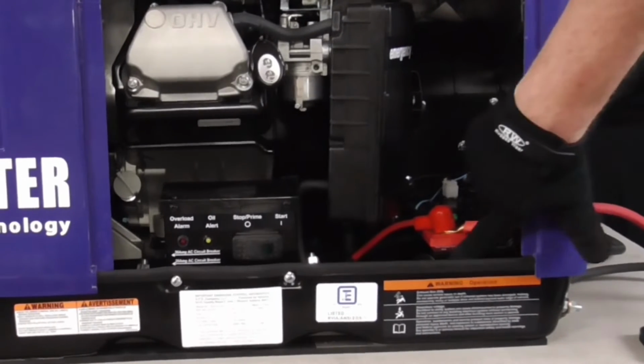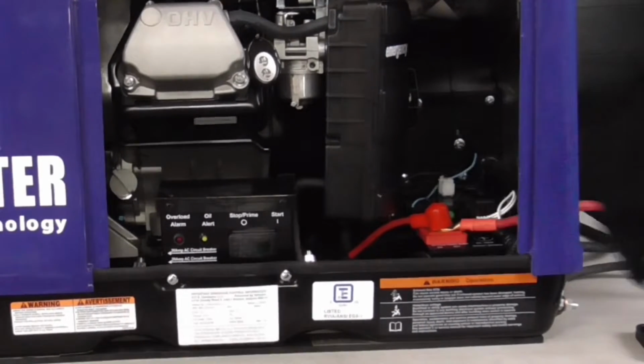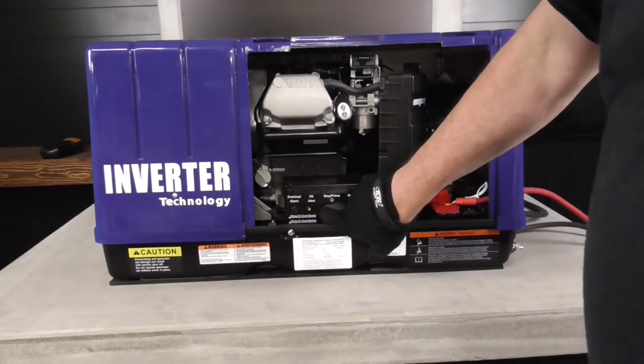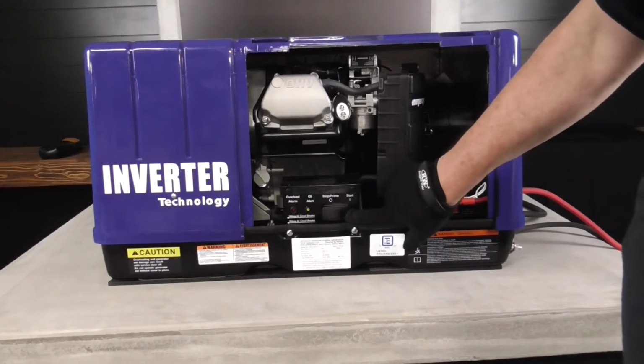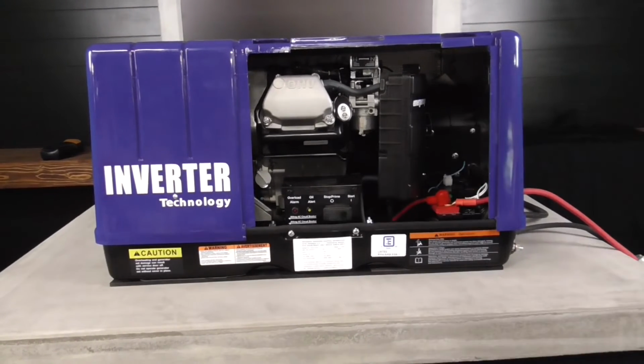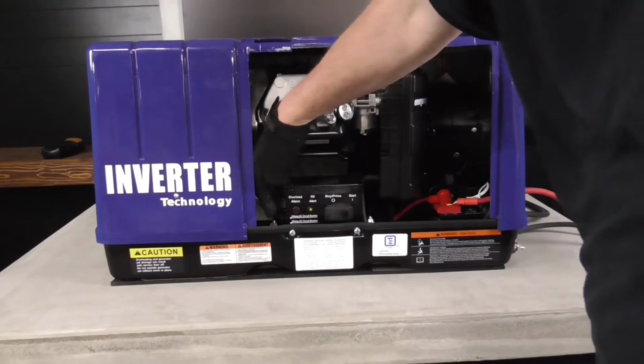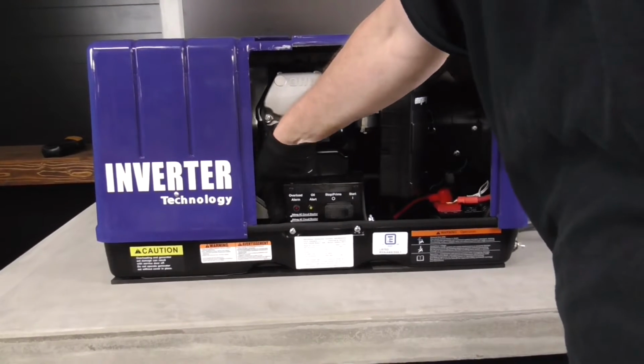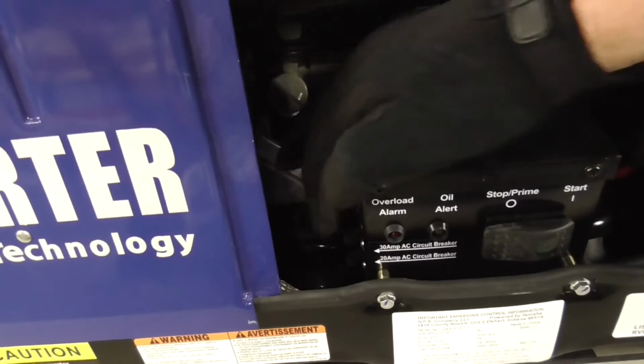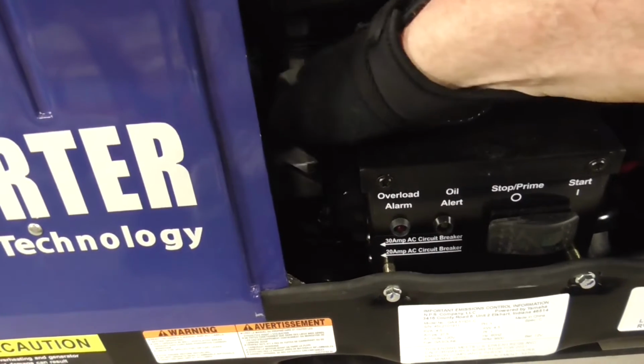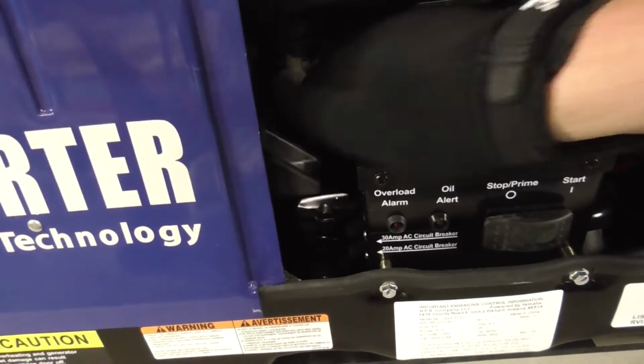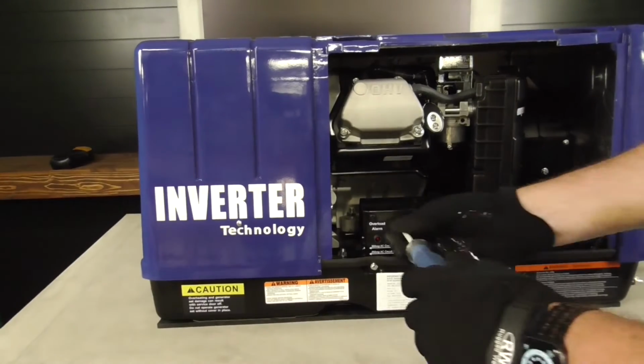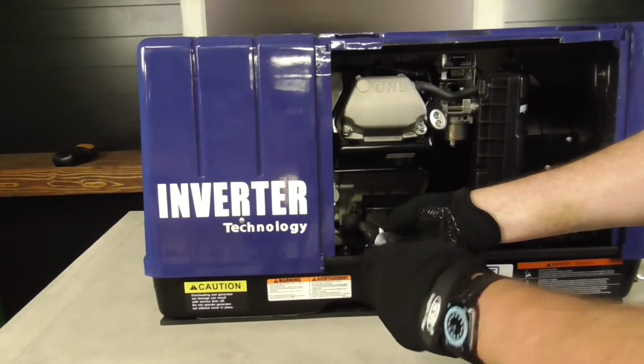When testing AC voltage, first make sure that the generator started, then make sure that the breakers are set. You can tell they're set by pushing them backwards towards the engine to turn them completely off, then pushing them all the way forward towards you to turn them completely on. If you still have no voltage in your system, check the breakers.